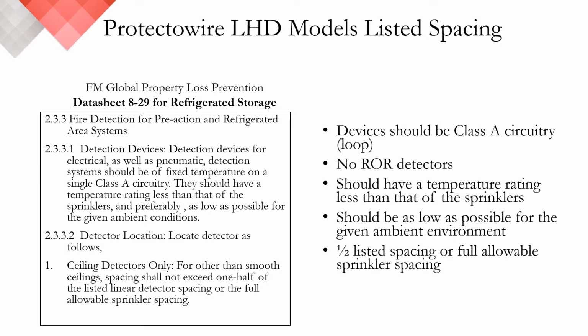Now, when a facility has smooth ceilings, the Protectowire can be located at the ceiling level up to our maximum listed spacing. For non-smooth ceiling types, the linear heat detector's listed spacing is reduced to 1/2 the maximum detector spacing or the fully allowable sprinkler spacing. Now, typically, the Protectowire is attached to and follows the ceiling sprinkler pipes. We're going to address that directly in a few minutes.